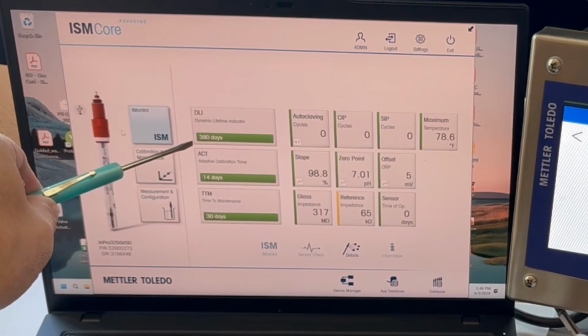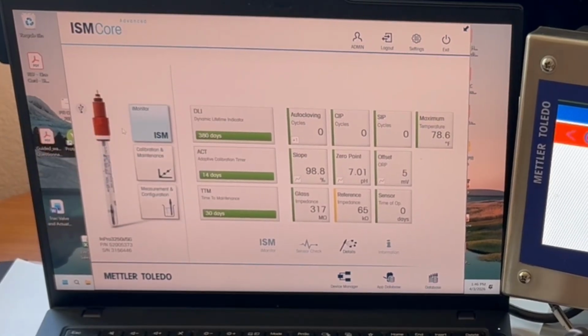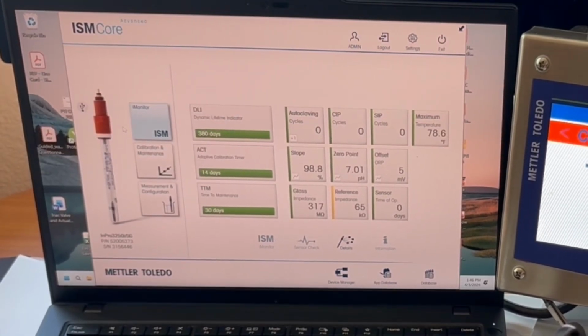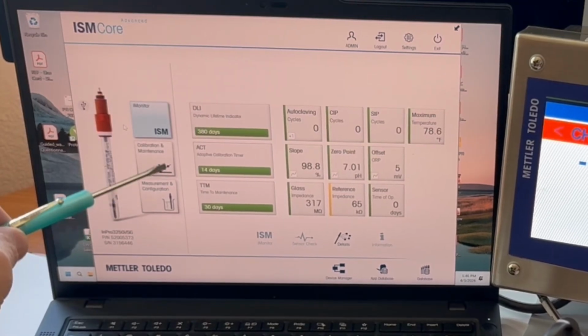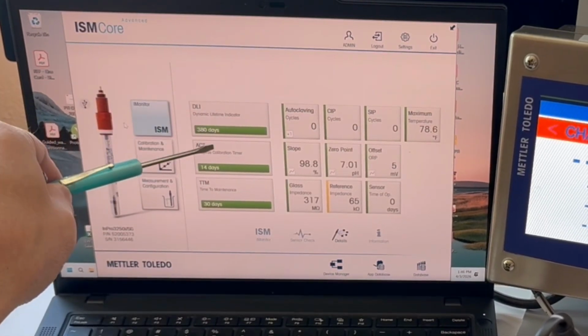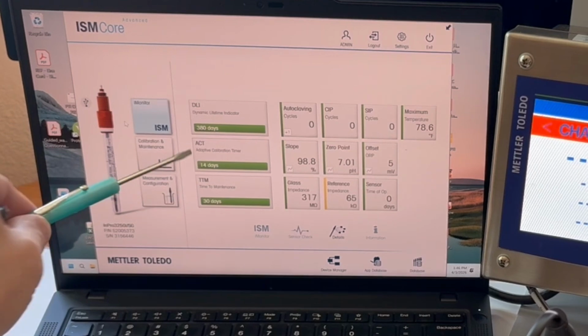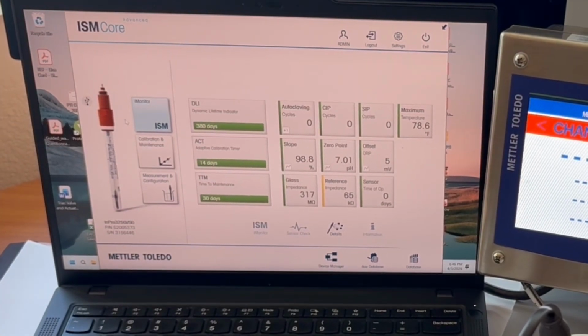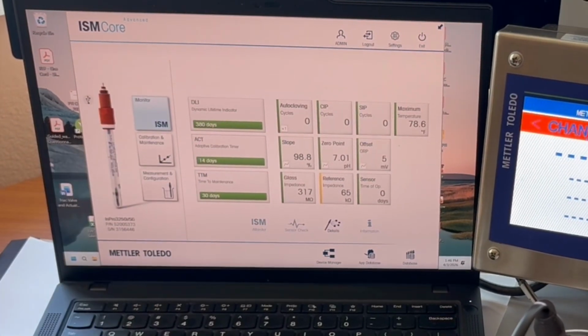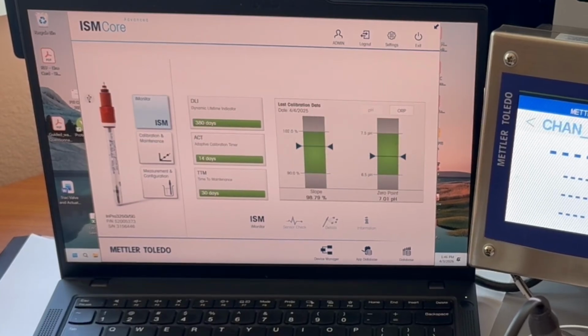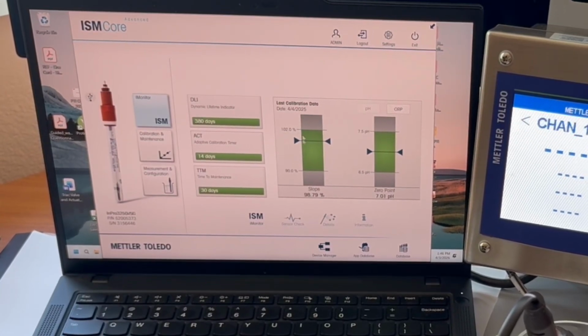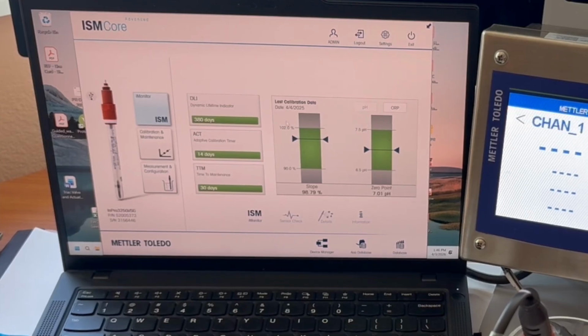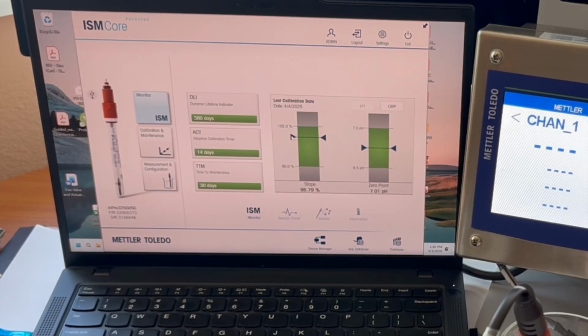According to this algorithm, it has 380 days left. This is a demo probe that's probably been in and out of a briefcase for 2 years, but it hasn't seen process, so a lot of the conditions are still really good. If we wanted to look at the slope and the zero, we can look at ISM monitor, and we can see a slope value anywhere between 90 and 102% is considered good. We can see where it sits.